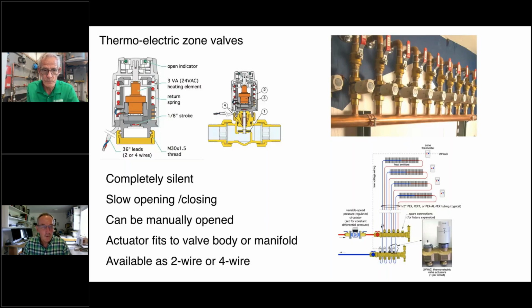And you were telling me too, once they're fully open, the inrush power, the actual motoring power, drops considerably to the standby power. It takes a lot to get the wax heated up, but once they're warmed up, we've got a little graph of that. I don't know if we put it in here, that shows how that power drops off once it's heated up and open. And one thing that you'll notice with this valve, if you've got them out in the cold garage, it's going to take a lot longer to heat up than if it's in your basement next to the boiler at 75 degrees, because again, you've got to get the wax from whatever temperature it is up to where it can expand and open the valve.